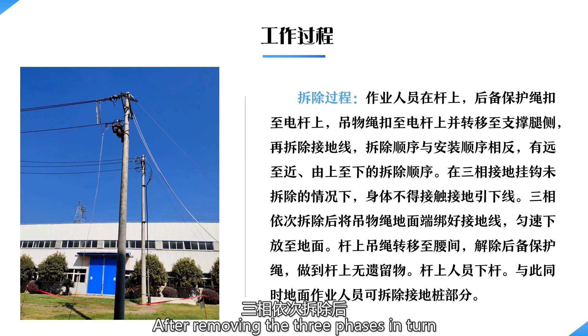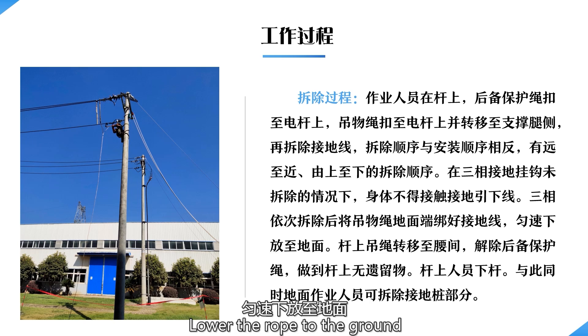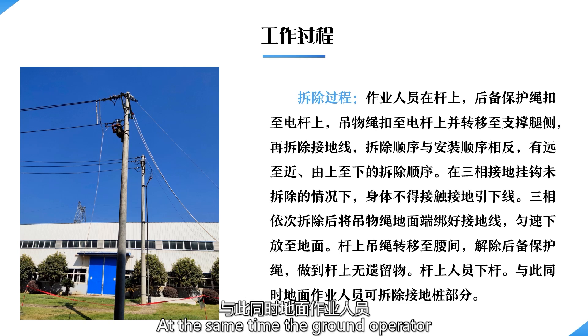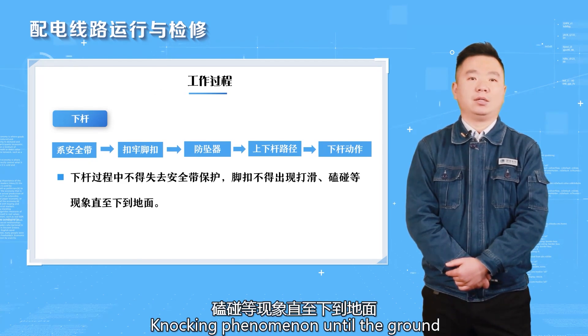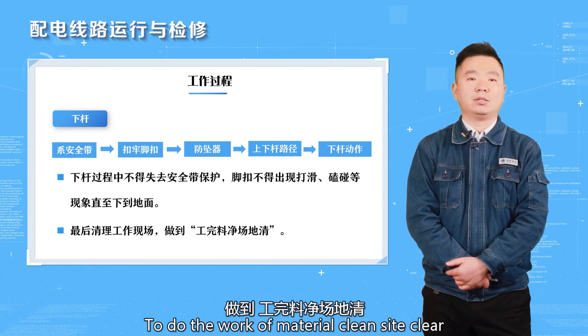After removing the three phases in turn, tie the grounding wire to the ground end of the rope and lower it to the ground at a constant speed. Transfer the lanyard on the pole to the waist and release the backup protection rope. Do not leave anything on the pole. Lower the personnel from the pole; at the same time, the ground operator can remove the grounding stake. No loss of safety protection during descent — the foot buckle shall not slip or knock. Once on the ground, clean up the work site and clear all materials.